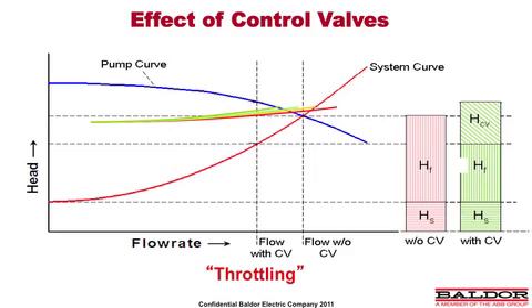Now the effects, we were talking about starting this circ water pump against a closed or partially opened discharge valve. How does that impact the pump performance and reliability and the load? Well, this next slide is going to show the effects of a control valve. And again, you will note, here's your system curve, that's the red line, the pump curve is a blue line. Now, let's look at the next screenshot, and you can see as that valve is throttled, you're pushing the pump back on the curve. And the more that pump is throttled, the further it moves back on the curve, loading up the pump, causing internal recirculation, high vibration, and shaking the intake structure in the motor. And further, you're also wasting energy.